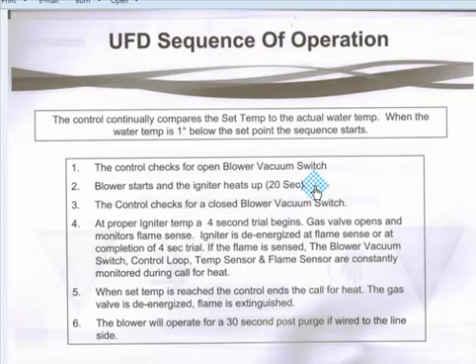Then the blower starts up, does a pre-purge. It makes sure that the vacuum switch is closing, all your safeties start passing checks. It goes through the millivolt and has to go through all the safety checks and everything else like that. Checks for the vacuum switch being now a closed switch. That means the tubing's good, the blower is good, pulling the correct vacuum, so it's going to close that vacuum switch.